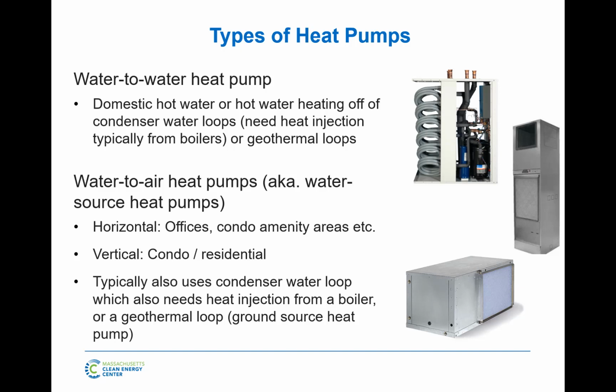Now, the word heat pump gets used for different things. There's what we call water-to-water heat pumps. Those can get used sometimes if you're trying to electrify your domestic hot water. So, for example, I have a geothermal loop. I want to use that to make hot water. Well, with a geothermal loop, the water will never come out of the ground hot enough for domestic use. I need to raise that temperature. So a water-to-water heat pump moves heat from colder water, which is geothermal, to the hotter water, which is domestic. It does not interact with air at all. It just goes from one water temperature to another and raises that heat, again, using a compressor, an expansion valve, an evaporator and a condenser. But they're not coils. They're usually coaxial heat exchangers, tube-in-tube heat exchangers.